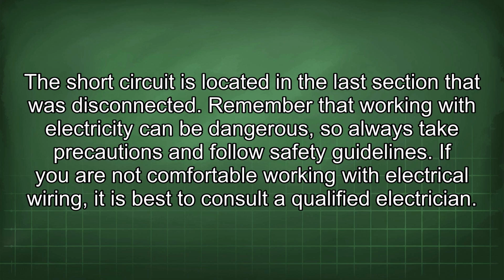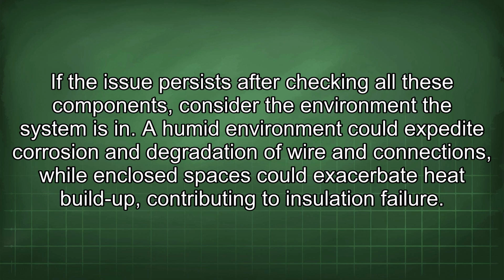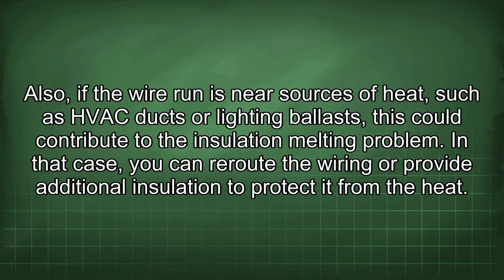Remember that working with electricity can be dangerous, so always take precautions and follow safety guidelines. If you are not comfortable working with electrical wiring, it is best to consult a qualified electrician. If the issue persists after checking all these components, consider the environment the system is in. A humid environment could expedite corrosion and degradation of wire and connections, while enclosed spaces could exacerbate heat build-up, contributing to insulation failure. Also, if the wire run is near sources of heat, such as HVAC ducts or lighting ballasts, this could contribute to the insulation melting problem.